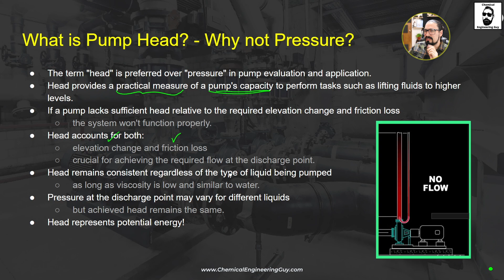Now, pressure does not account directly for friction losses or changes in velocity or height. It is only a parameter, remember. But head does account for all those parameters. We account for friction loss, elevation change, pressure changes, velocity changes, and so on. Head remains consistent regardless of the type of liquid being pumped. As long as viscosity is low and similar to water, you can compare several pumps and verify whether or not they are going to perform as required.